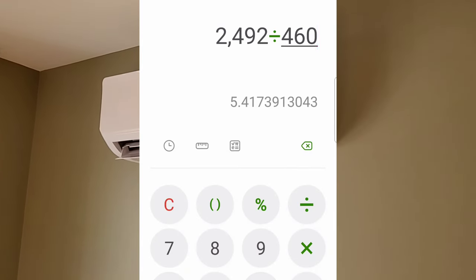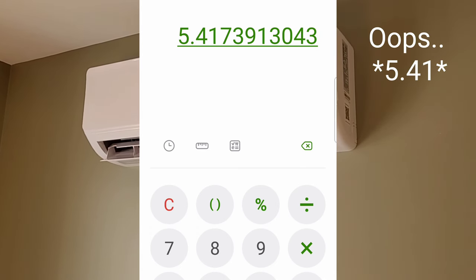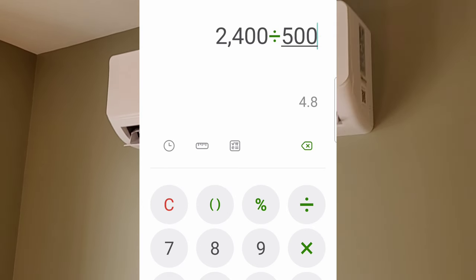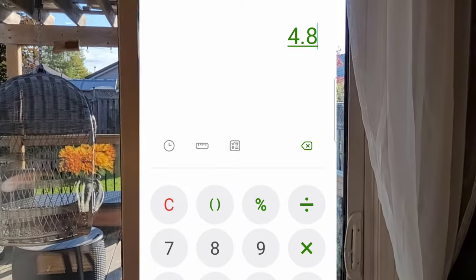Now that we have all our information, we take our output wattage divided by our input wattage, giving us a coefficient of performance of 5.41 — which is extremely high. For anyone doubting the numbers, taking slightly lower output and higher input still gives us a COP of 4.8, which is again very good.